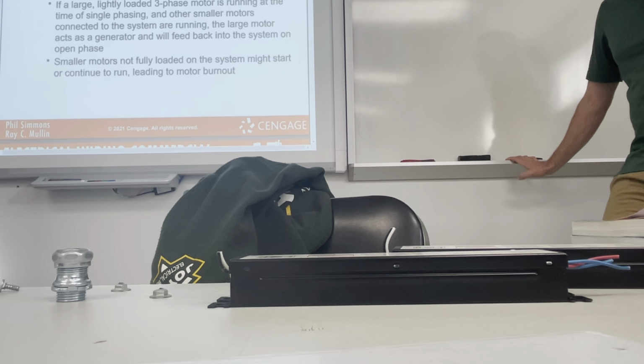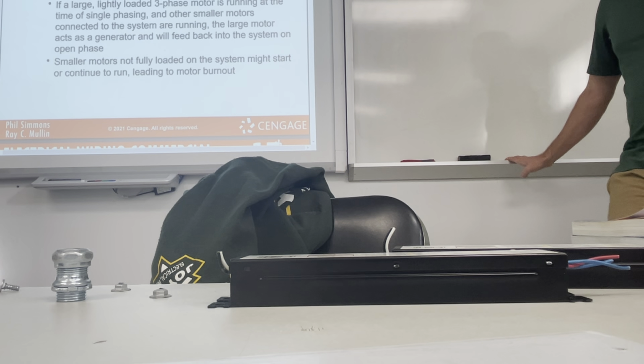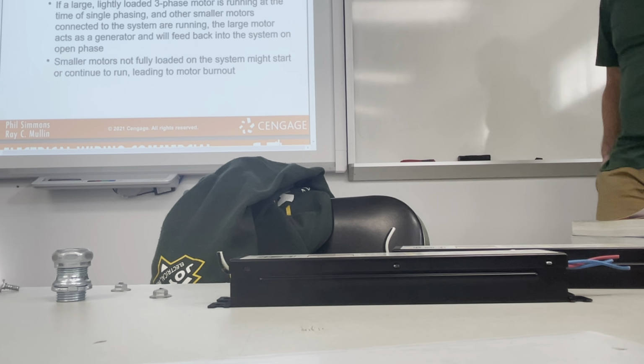If a large, lightly loaded three-phase motor is running at the time of single phasing, and other smaller motors connected to the system are running, the large motor acts as a generator and will feed back into the system on open phase. Interesting. Smaller motors not fully loaded on the system might start or continue to run, leading to motor burnout. Yeah, so like a three-phase motor is actually nothing more than a generator, believe it or not.